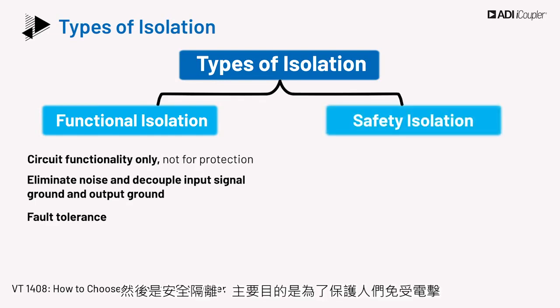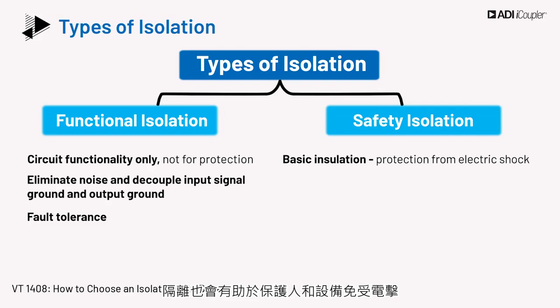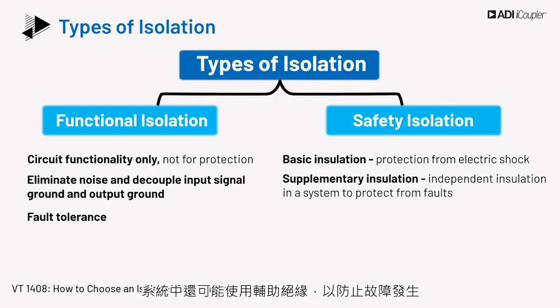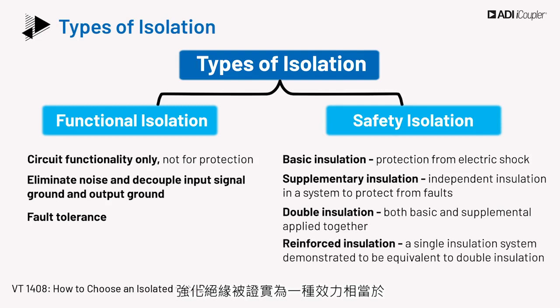Then there is safety isolation. This is required primarily to protect people from electric shock. There is low voltage electronics and user operation on one side and higher power levels at the switches. Isolation also helps protect people and equipment from electric shock. Apart from basic insulation, supplementary insulation may be present in a system to protect against faults. There is double insulation, which is both basic and supplemental applied together. Reinforced insulation is a single insulation system demonstrated to be equivalent to double insulation.